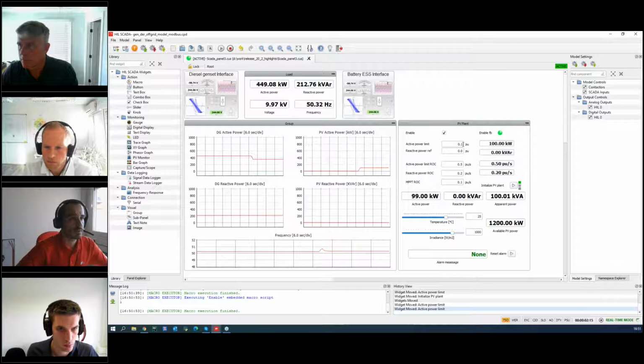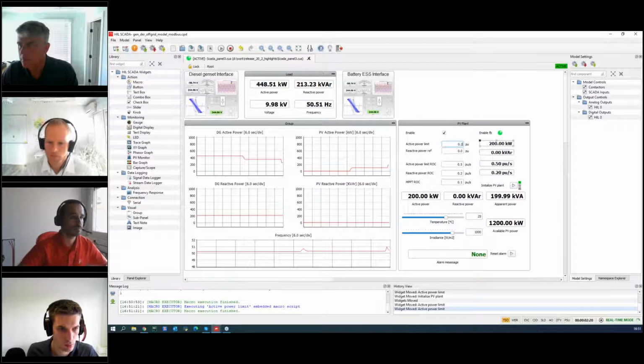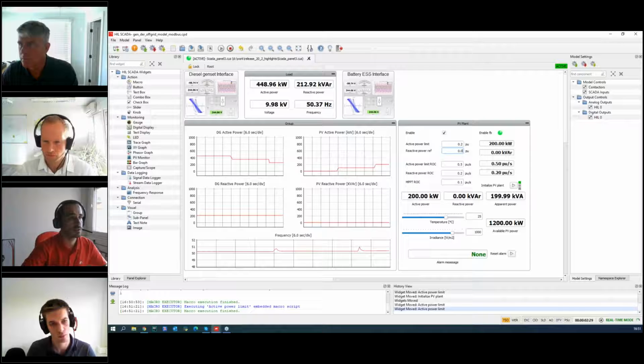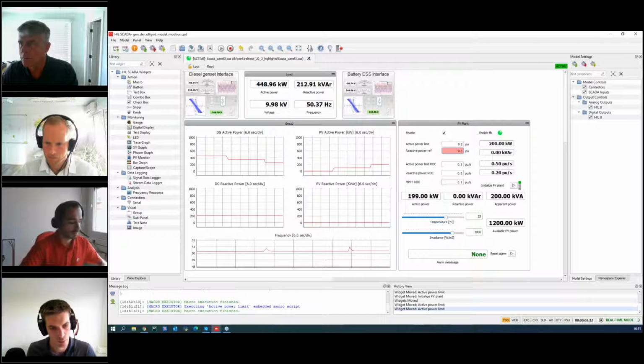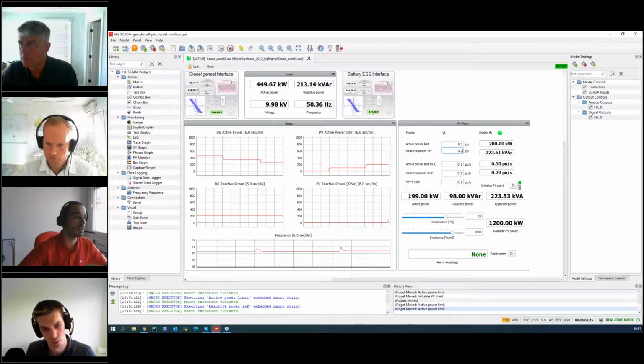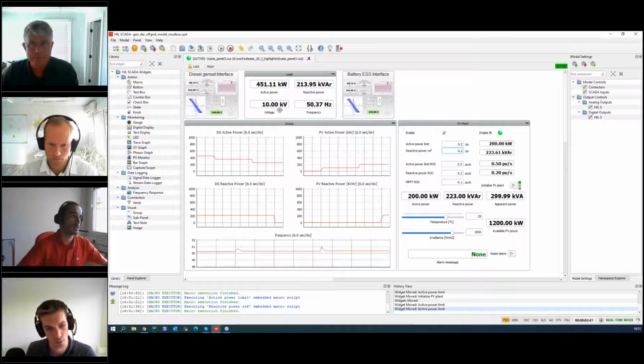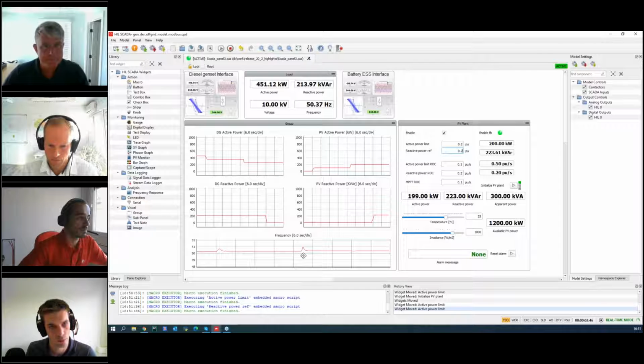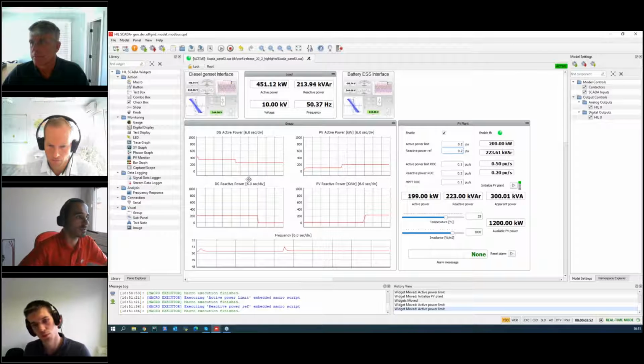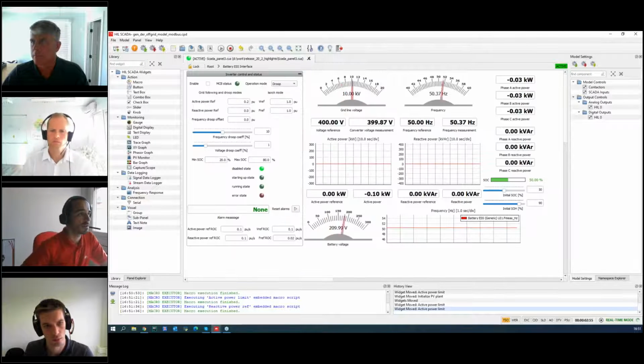So what we can do is change the reference here for the active power limit, to put more PV power into the system, and also support the system with a little bit of reactive power. Let's say 0.2 per unit. Now we can see that because of this reactive power, our voltage on the bus increased a little, which is expected. Also on the graph at the bottom, we can see some dynamics in the frequency due to the changes that we introduced in the system.